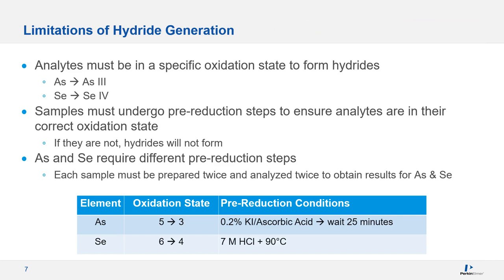Hydride generation does have some limitations. The analytes must be in a specific oxidation state to form hydrides. For example, arsenic must be in the plus-three state and selenium must be in the plus-four state. Arsenic in the plus-five state will form hydrides a little but not very efficiently, and selenium-6 will not form hydrides at all.